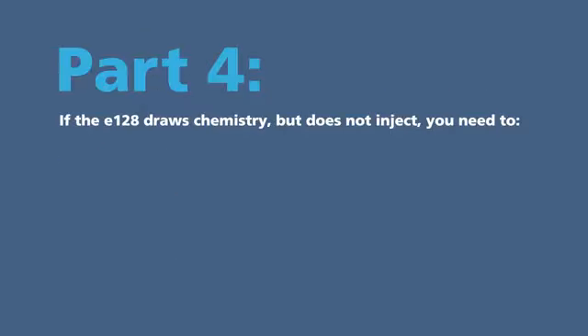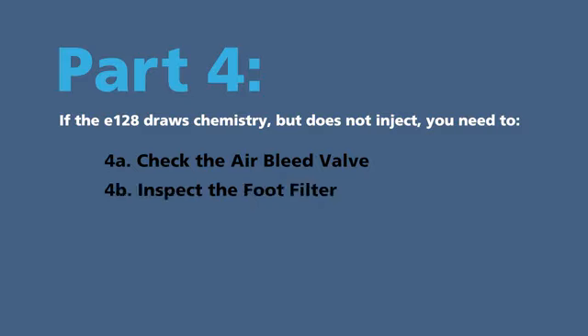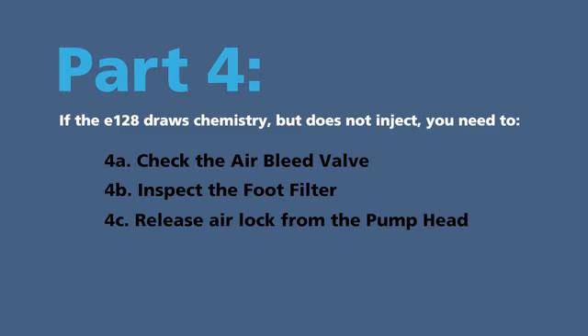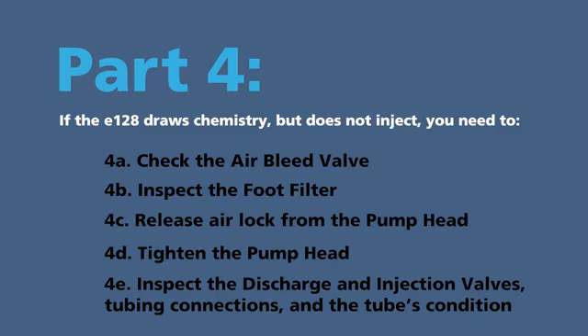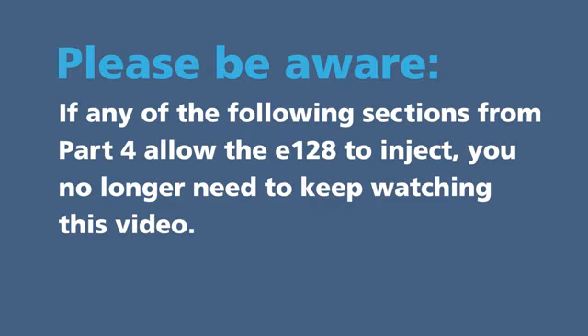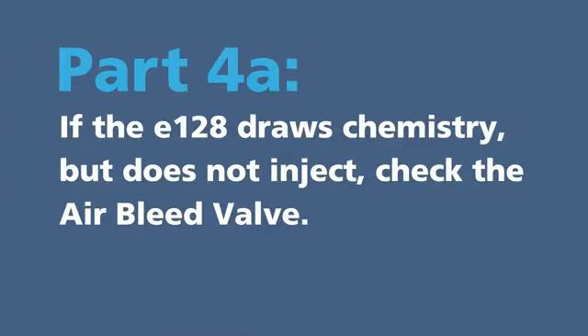Part 4. If the E128 draws chemistry but does not inject, you will need to: 4A. Check the air bleed valve. 4B. Inspect the foot filter. 4C. Release airlock from the pump head. 4D. Tighten the pump head. 4E. Inspect the discharge and injection valves, tubing connections, and the tube's condition. If any of the following sections from Part 4 allow the E128 to inject, you no longer need to keep watching this video.